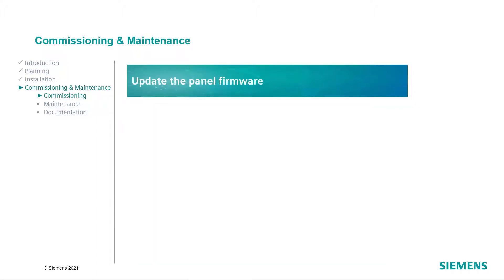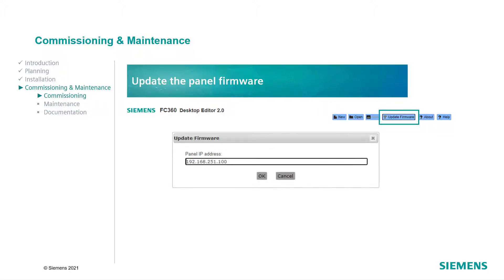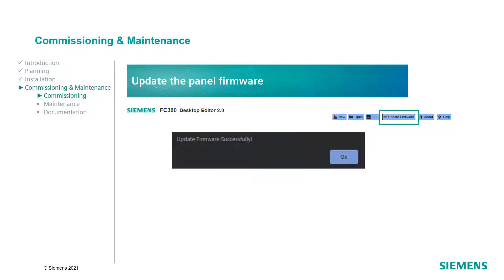The panel firmware should be kept up to date. To initiate the update, make sure to have the latest version of the FC360 Desktop Editor installed. Verify that the firewall rules are set correctly and connect the panel to the PC. Open the Desktop Editor and click on the Update Firmware button. Then set the panel to Access Level 3 and confirm the pop-up message. The firmware will now be updated, and a message will be displayed to indicate if the update has been completed successfully.